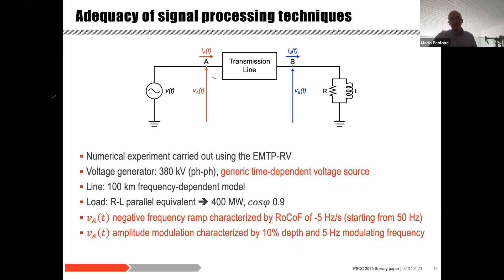So we have a 100-kilometer line with a frequency-dependent model. Everything is modeled in a time domain simulator, in this case the EMTP-RV. Then the transmission line is feeding a constant impedance load, a constant time domain parameter model of the load that at 50 hertz and 380 kilovolts is absorbing 400 megawatt with a lagging cos phi of 0.9. What we wanted to do is to reconstruct the power that is transmitted by this system to the load, where the supplying voltage is experiencing, for instance, a frequency ramp with a rate of minus 5 hertz per second, or an amplitude modulation of 10% in depth at 5 hertz modulating frequency.